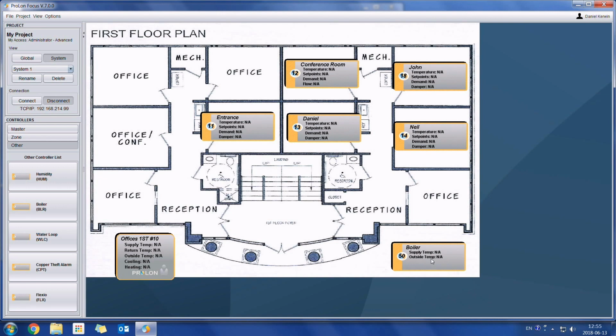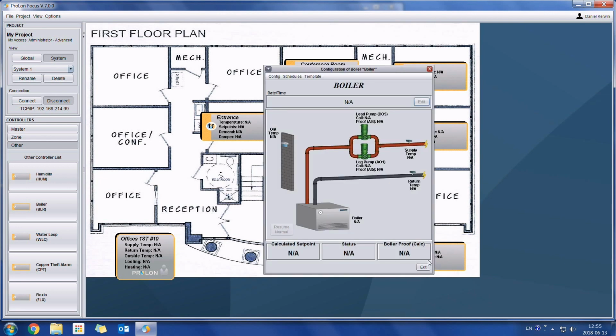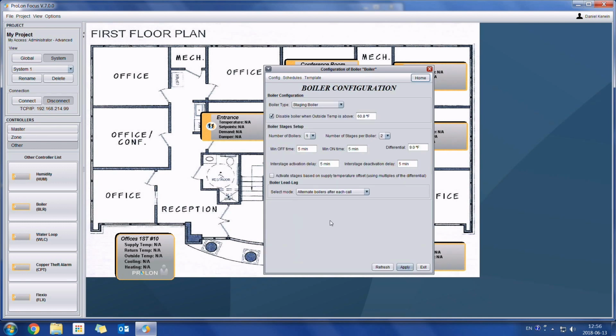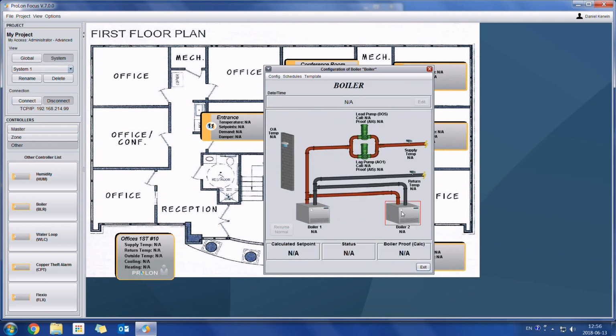Okay, so if I double click on the boiler, here are the default graphics of our boiler. We can see we have 2 pumps and our boiler right here. We're monitoring the temperature in the supply and the return, as well as the outside air temperature. Now, if I double click on the boiler, we can choose how many boilers there are, as well as how many stages. So we could have 1 boiler with up to 4 stages. We could have 2 boilers with up to 2 stages each. So if I press apply, here I have our 2 boilers.